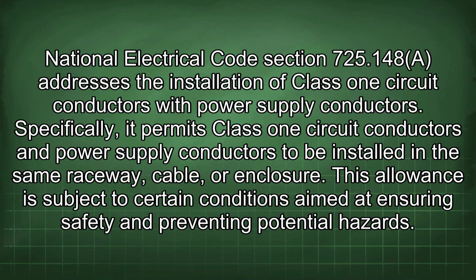National Electrical Code Section 725.148 addresses the installation of Class 1 circuit conductors with power supply conductors. Specifically, it permits Class 1 circuit conductors and power supply conductors to be installed in the same raceway, cable, or enclosure. This allowance is subject to certain conditions aimed at ensuring safety and preventing potential hazards.